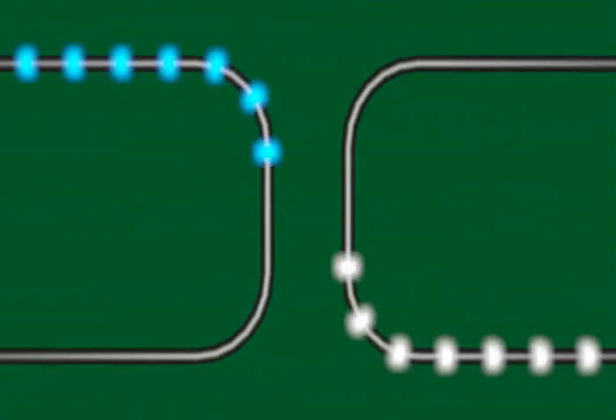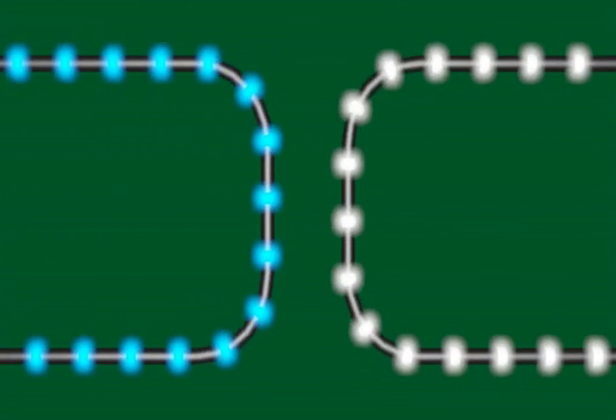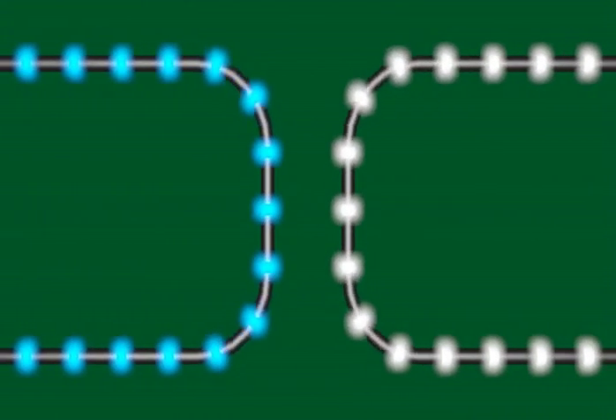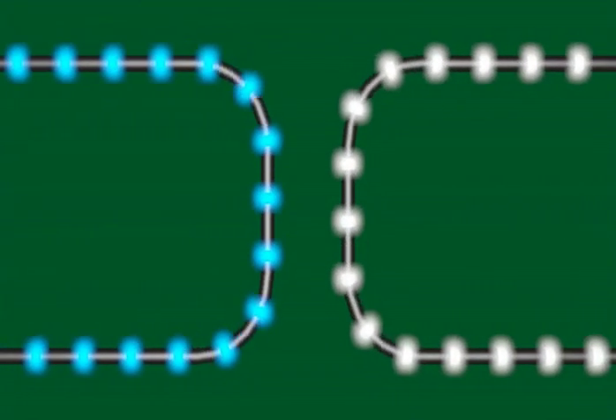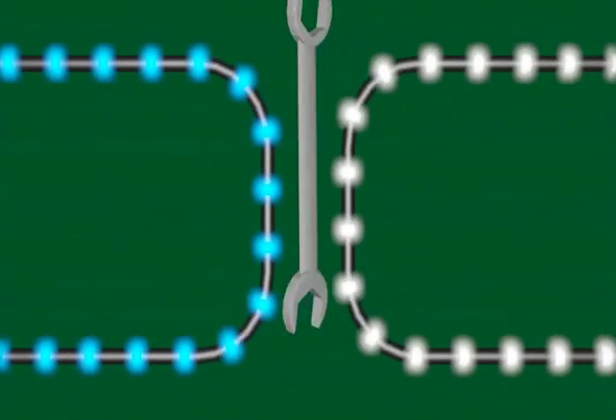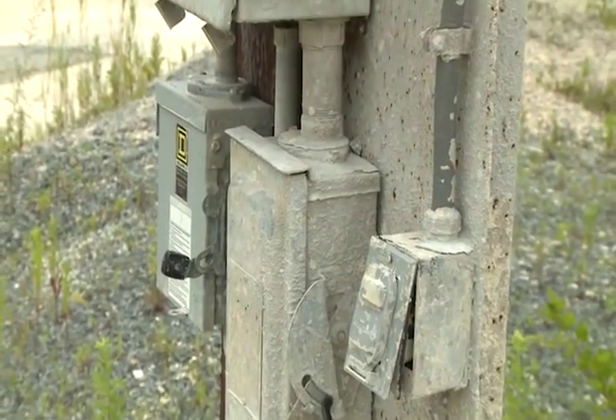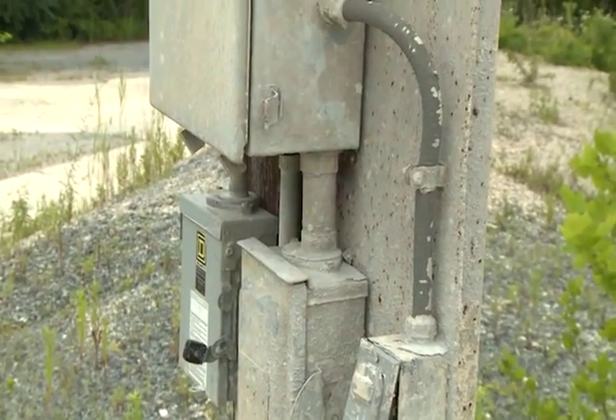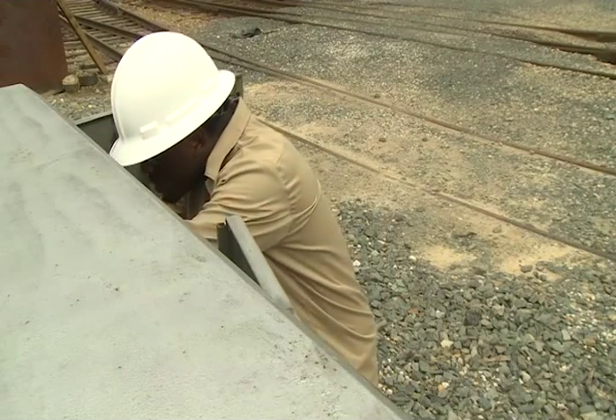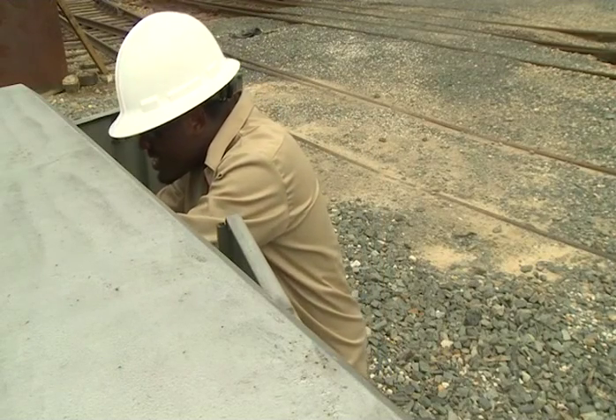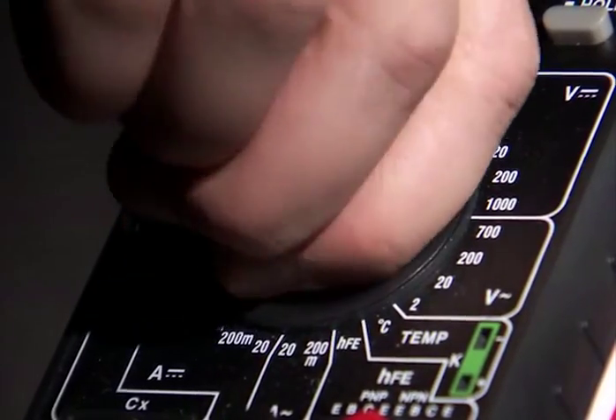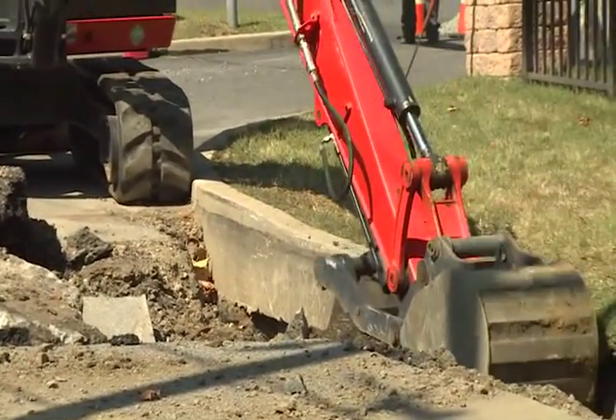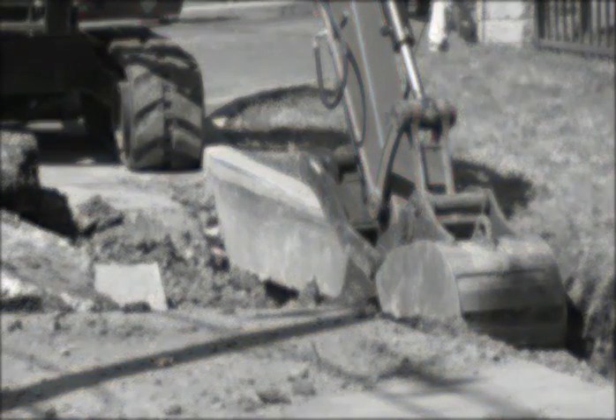Most of the time, energy moves safely through electrical systems, unless something happens to divert the power. When diverted electricity jumps through the air from contact to contact, or from a contact to ground, that's an arc flash. This can occur spontaneously when corrosion or conductive dust builds up in equipment. But most arc flashes result from mistakes that are made when someone is working on or near an electrical system. Touching a probe to the wrong circuit, or dropping a metal tool into the system, even digging a backhoe into an underground cable can all cause arc flash.